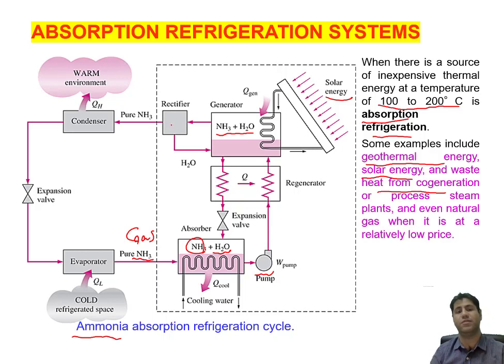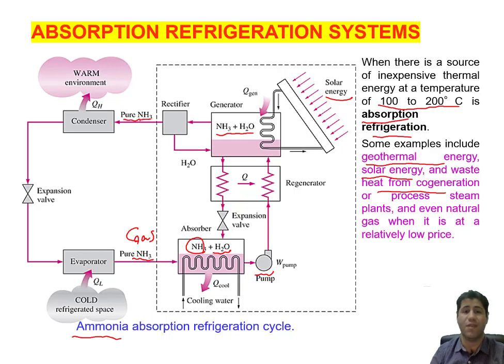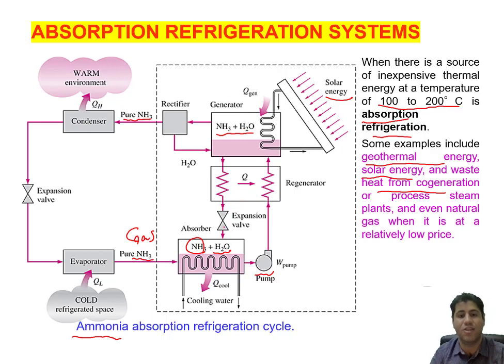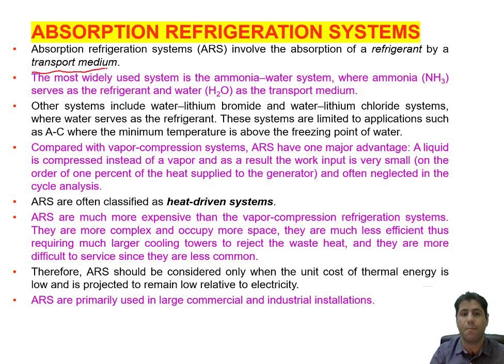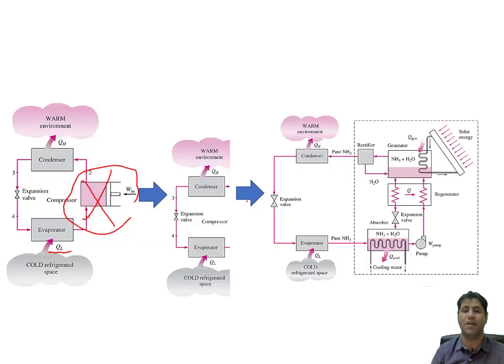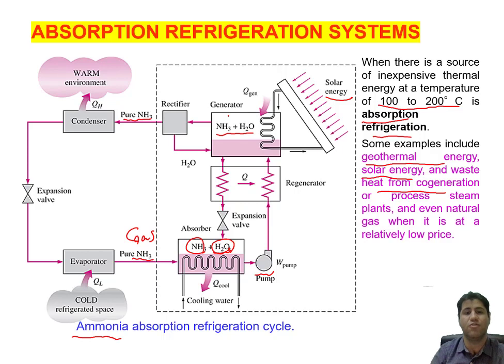The separated ammonia is sent to a rectifier, which is designed to prevent water from entering the condenser. Then pure NH₃ — now at higher pressure — is introduced to the condenser. The compression effect here is achieved by transportation: water acts as the transport medium, carrying ammonia from the absorber to the generator.